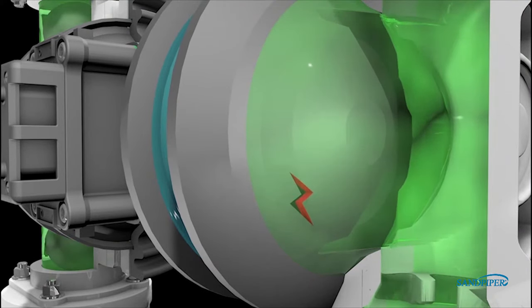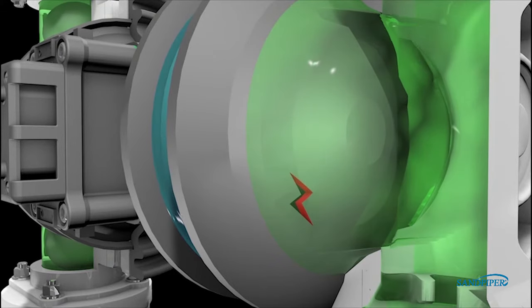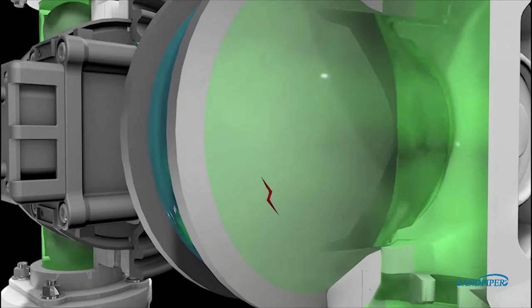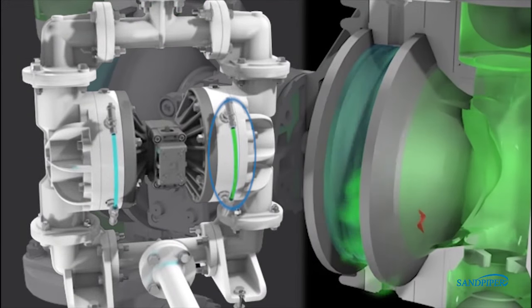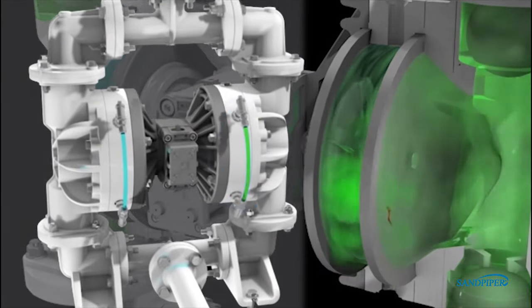In the event of a pumping diaphragm failure, the process fluid will enter the containment chamber causing the fluid to change color. This will alert the operator that the pumping diaphragm has failed and that maintenance is required on the pump.